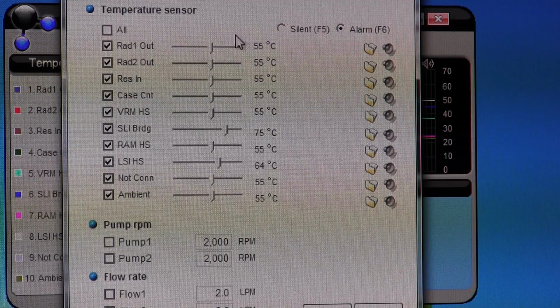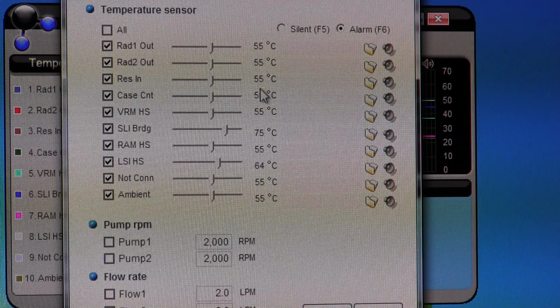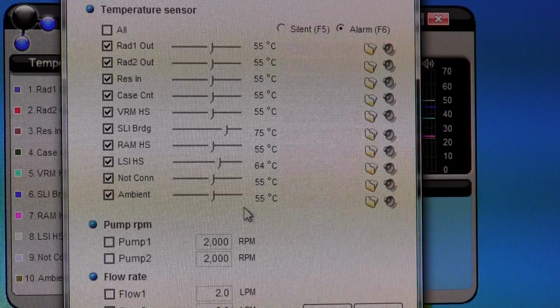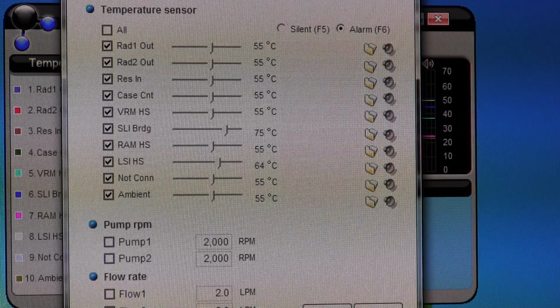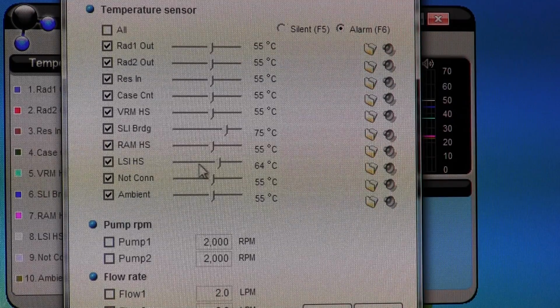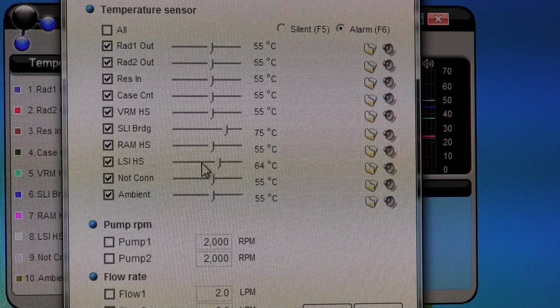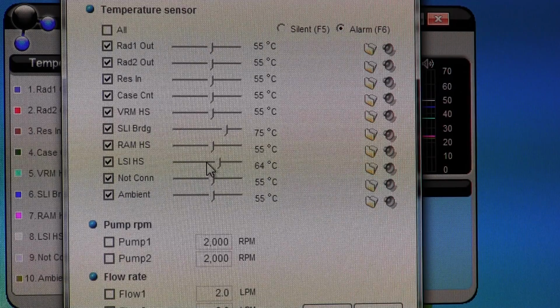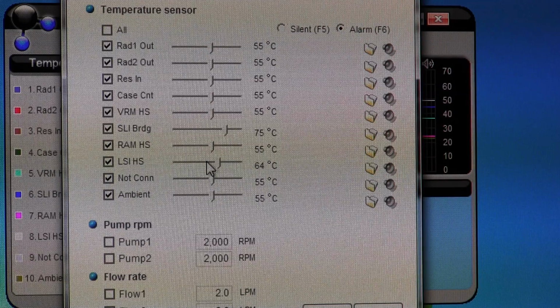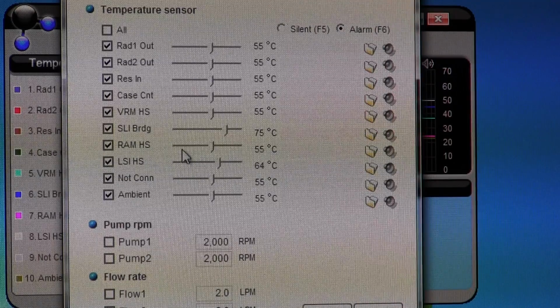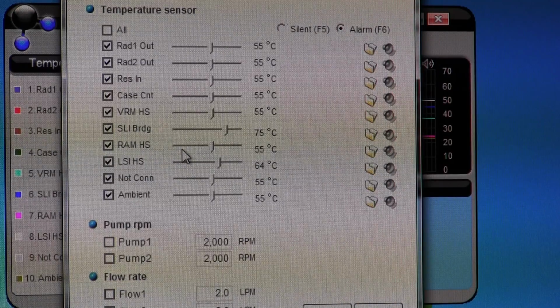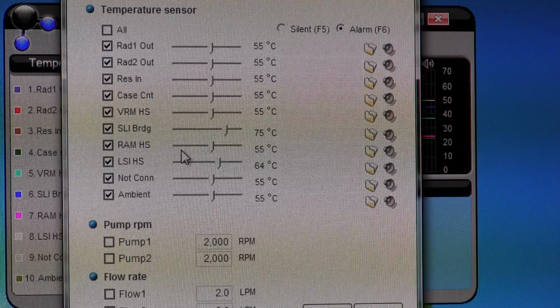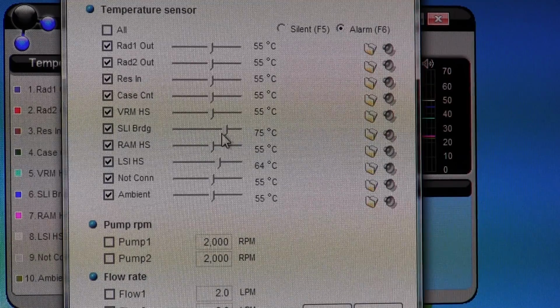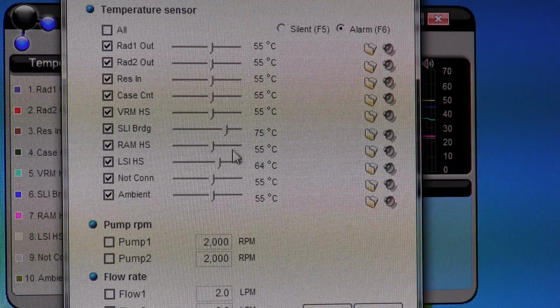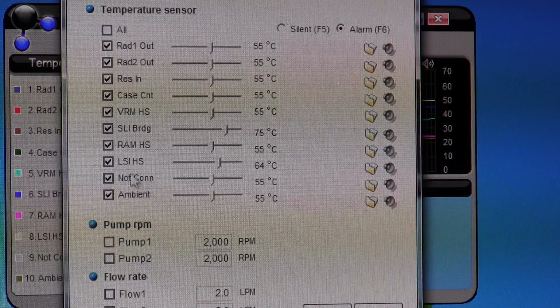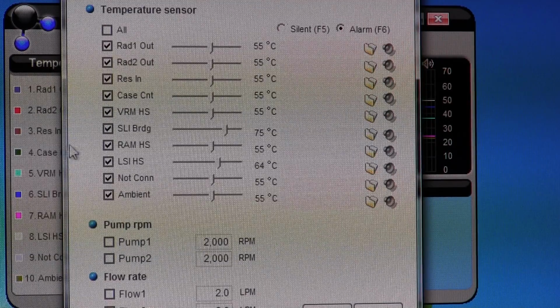Well, that's because out of the box the system defaults to 55 degrees C for an alarm. The LSI controller runs at about 50, 52. I don't know if you saw it before, I showed 50-some degrees, and when I didn't have my fans blowing down on it, it crept up to 55, 56, so it was going off. So you can adjust the alarm setting, and I'll actually do that now.